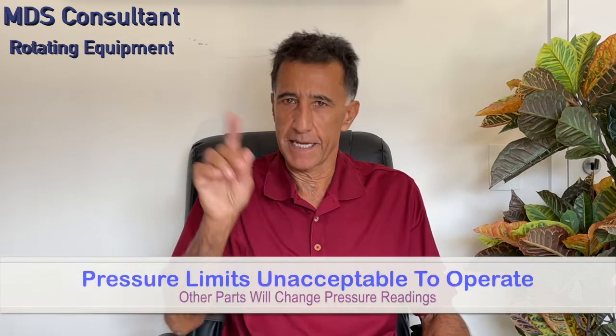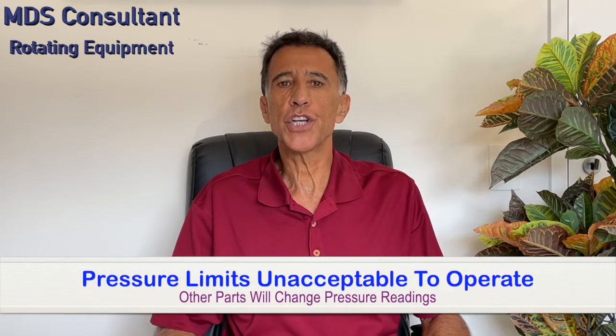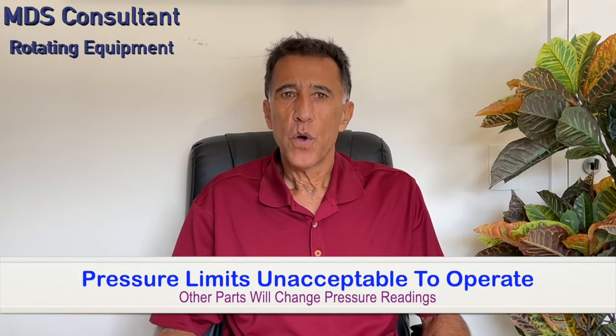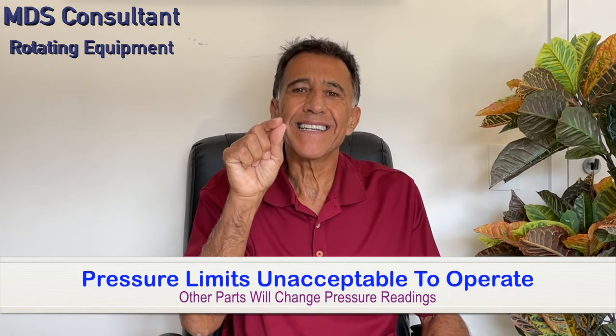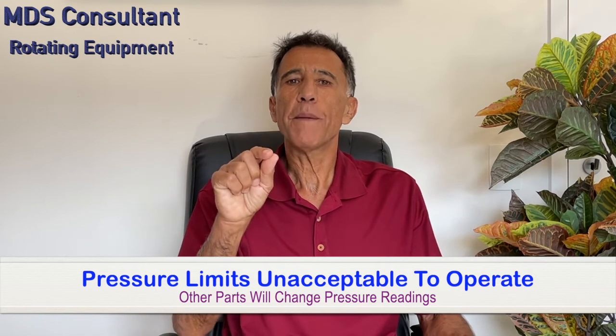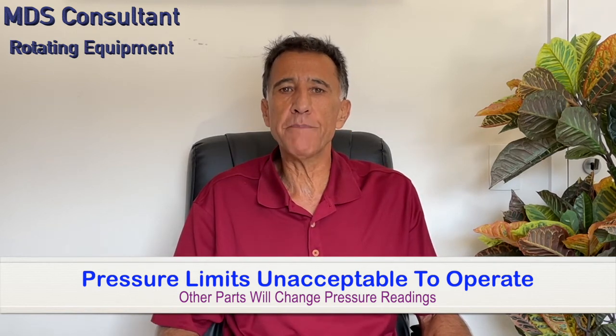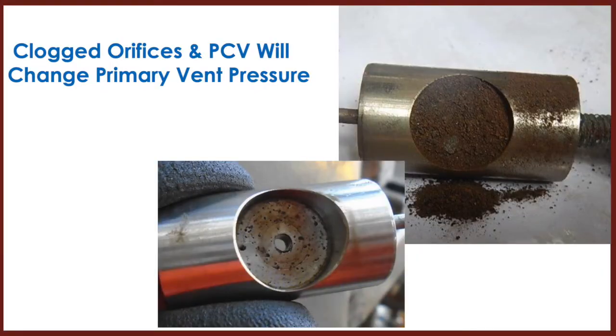Now let's say you've determined primary vent pressure readings are just unacceptable and beyond changing the limits. Well, first, you're going to have to make sure it's not the seal itself. There are other parts that could easily affect the primary vent pressure, like clogged or dirty orifices or pressure control valves. Let's say you've checked everything else and still readings are way out. Does it really mean you have to yank it out? Not so fast. You have a couple of options that I've had pretty good success with.